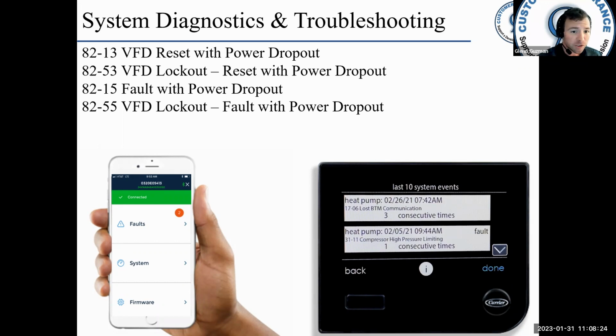You can get these faults due to line voltage loss. Okay, 4 occurrences within 1 hour gives you the lockouts, which result in a 2-hour lockout. Like I said, momentary power loss, electrical noise. You might see these paired with other electrical noise codes. Of course, check some of the obvious stuff, right? Check the tightness of your connections, all the way up to the VFD itself. You could have power issues with afternoon storms, connections, something like that.